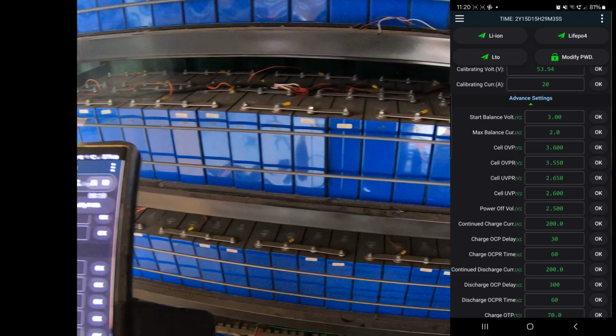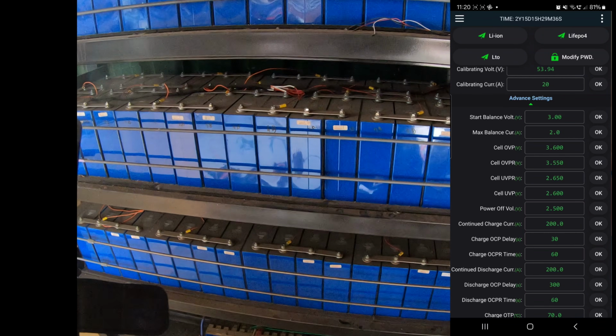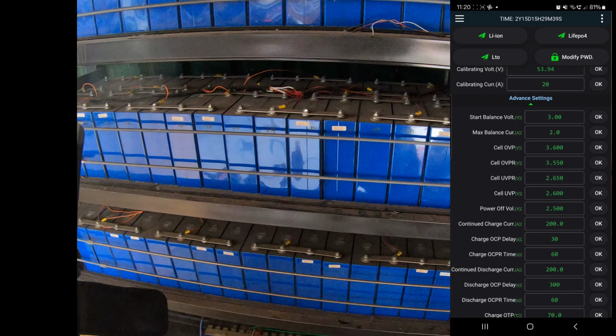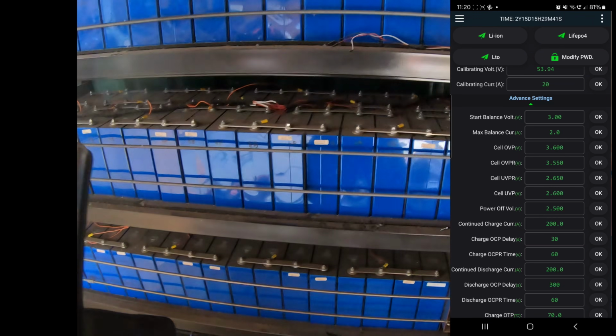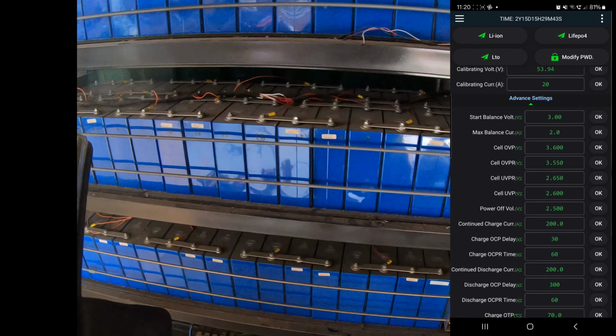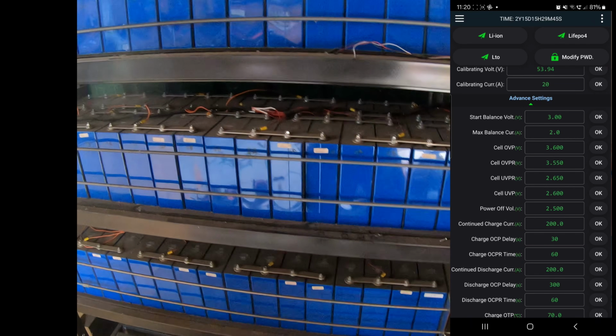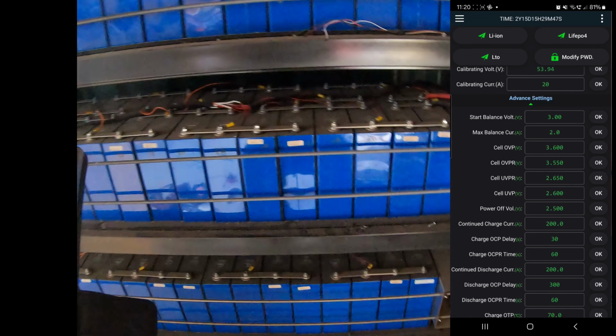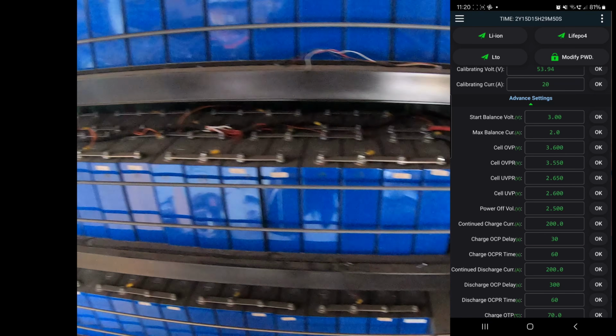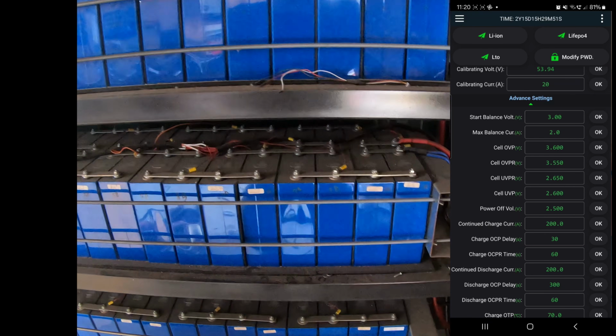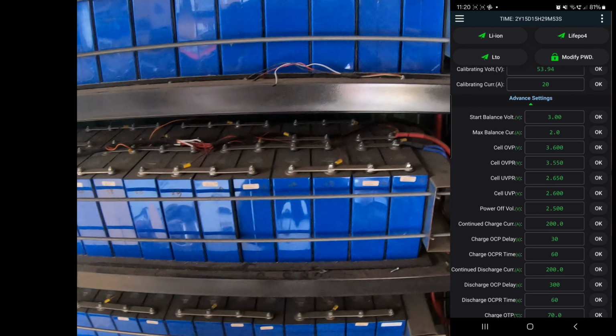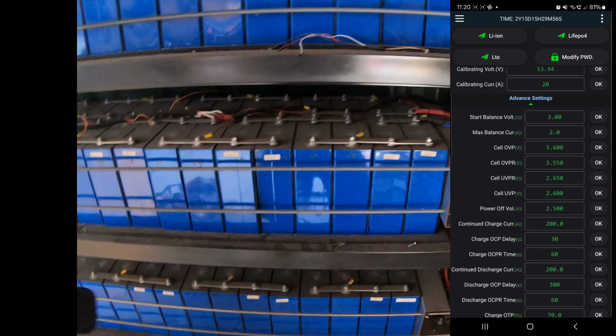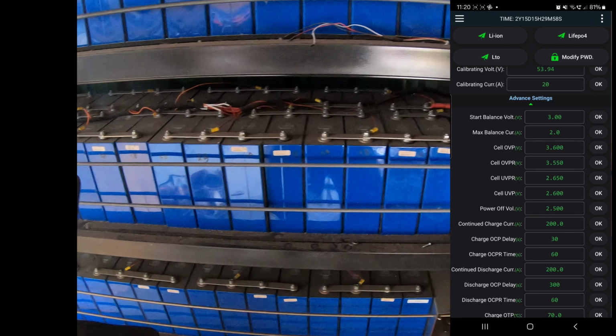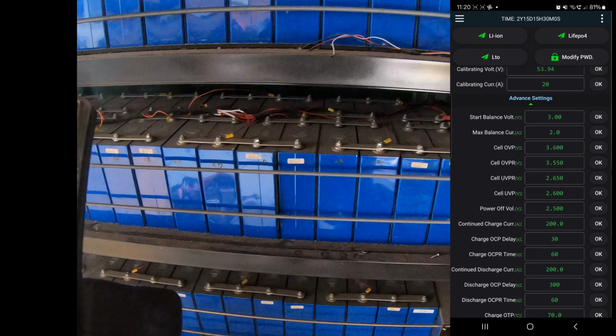The over voltage protection is set to 3.6. The cell over voltage protection reset is at 3.55. Now that's probably slightly high, but when we're cramming in as much power as we can, like if it's been overcast and we're trying to get power into the battery in a really short period of time, when they block charge, we want that to reset as quickly as possible so we can throw some more power in. That's a gamble that we're taking. We wouldn't expect everybody to do it the way we're doing it, and we're happy with it.